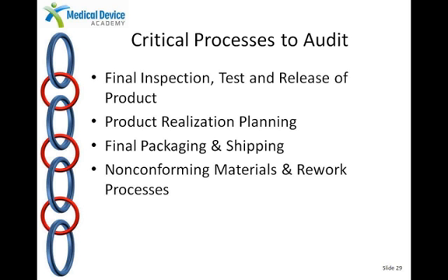The incoming inspection person said, every single time I get their orders in, they make a box for us, and it has all the computer controls in and the software, and then we integrate it with the rest of the system. But they get the packaging. Sometimes it's got corner protectors, sometimes it doesn't. Sometimes it's scratched, sometimes it's not. Sometimes it's got a certificate of analysis, sometimes it has a device history record, sometimes it doesn't. So every single time I get it differently, they can't seem to package it the same way twice. That's a problem. It's preventing me from transferring stuff to manufacturing, and I have to expedite everything.